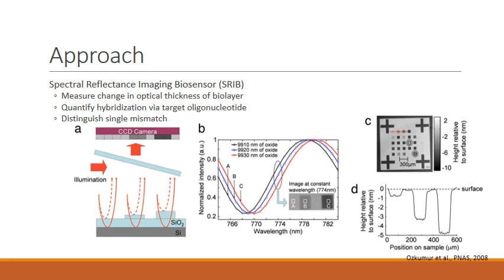Once the image is taken by the camera, it is recorded as an intensity image over varying wavelength steps to form a reflectivity versus wavelength curve for each pixel on the recorded image. The result of this would be a reflectivity versus wavelength curve for each of the different optical paths. The data from these curves can be processed to show the thickness of deposited biomolecules per pixel.